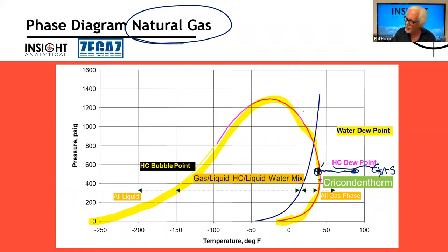The other piece on this graph is the water dew point as well. So this is the water curve right here. So in the particular case we were looking at there, if we started over here and we cooled it down, when we hit this temperature here, which was maybe 40F, we were at our first condensation of hydrocarbons. If we continued to cool it down and got to this point, water would start to condense out.